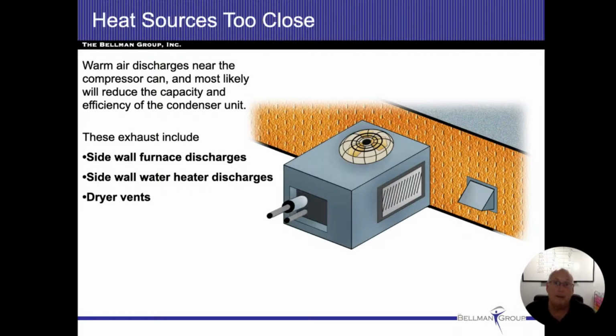However, the condensation that comes off of a sidewall vented furnace, because it is a condensing furnace, that condensation is very caustic. And if that gets blown onto the fins on a regular basis in the winter, we're going to start rotting and deteriorating those fins like there's no tomorrow. So that in itself, I think, is a big deal. And yeah, the air shouldn't be blowing on the fins. It should be off to the side somewhere.